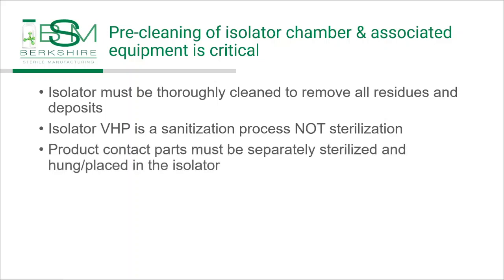It should also be pointed out that all product contact parts must be separately sterilized and hung or placed in the isolator. I have heard of some companies leaving stopper bowls in and using a sanitization of the isolator to, quote, sterilize the bowl. That is not a good practice and should be avoided. All product contact parts must be sterilized.